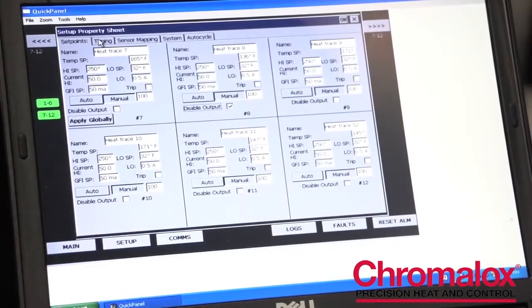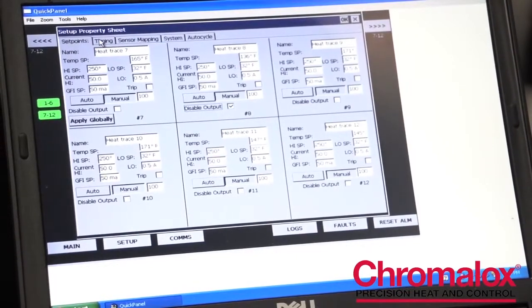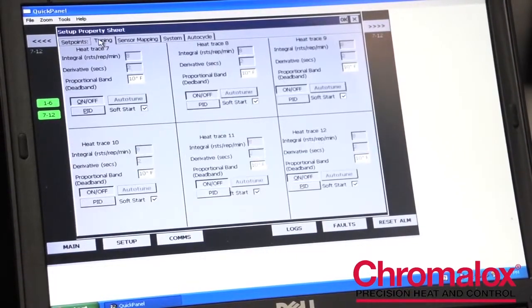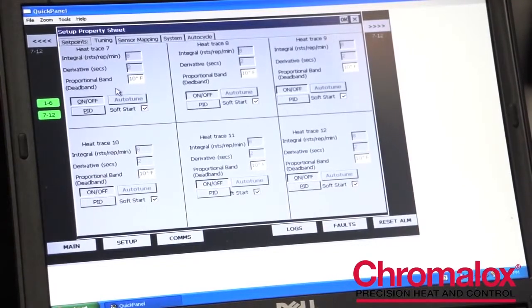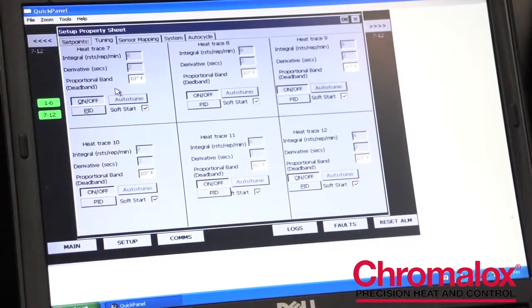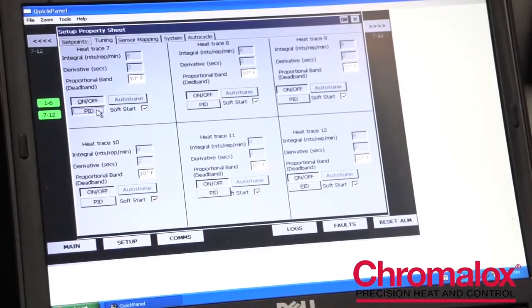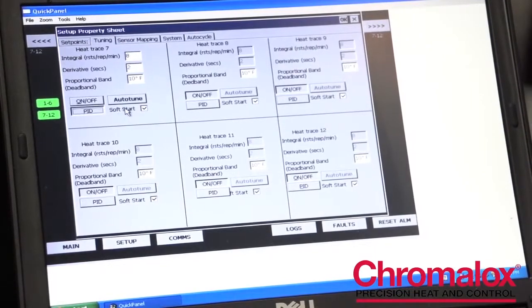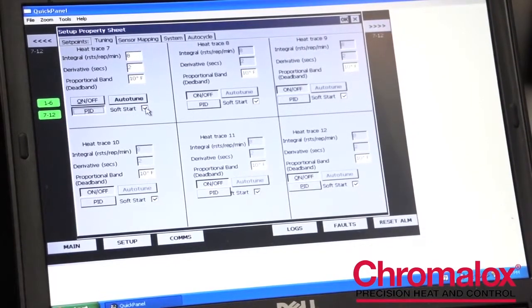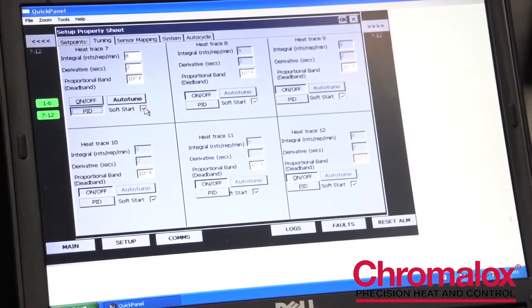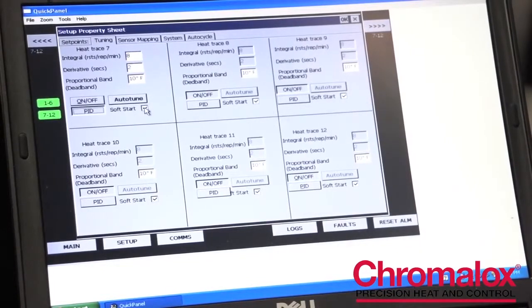The next tab is the tuning tab. In the tuning tab, one can choose how the control controls the heaters, whether it's an on off control or PID control. This is also where you can select your soft start function. You can actually turn it off if you have a non heat trace application.